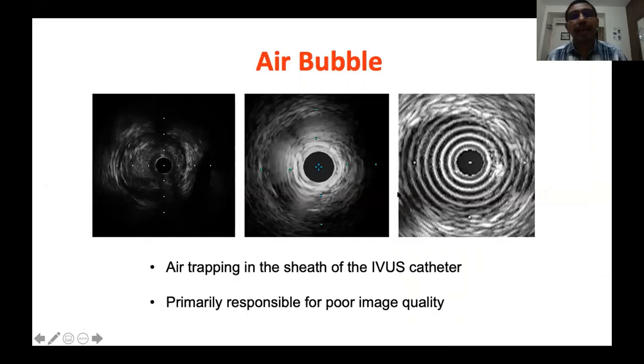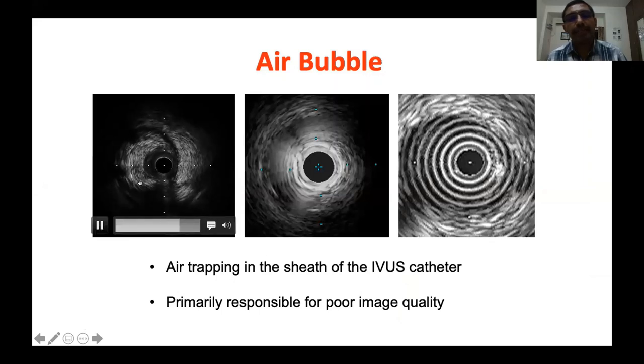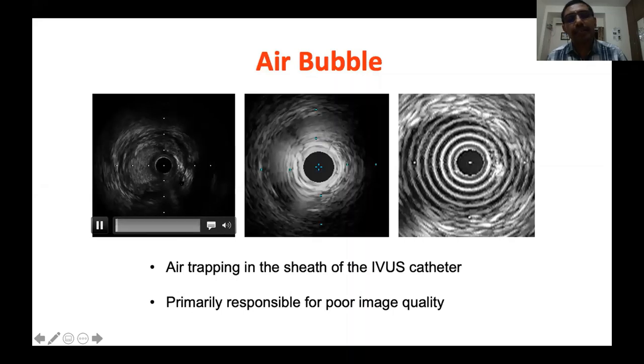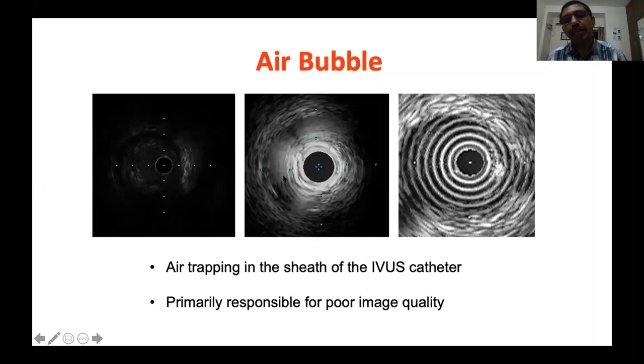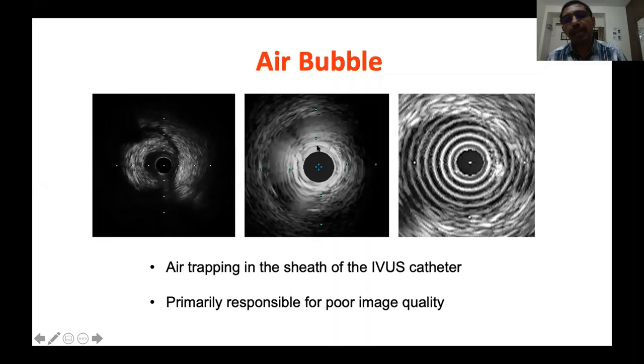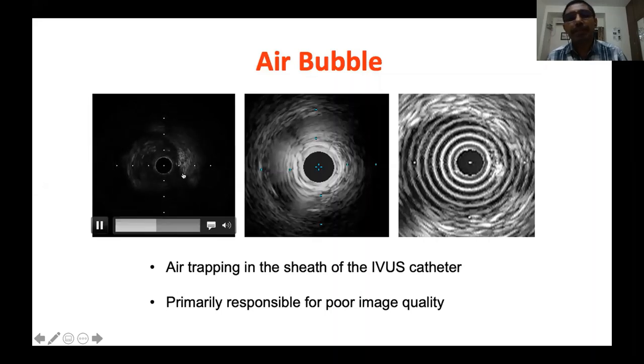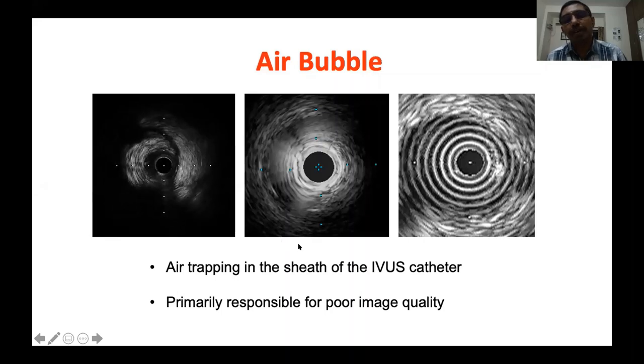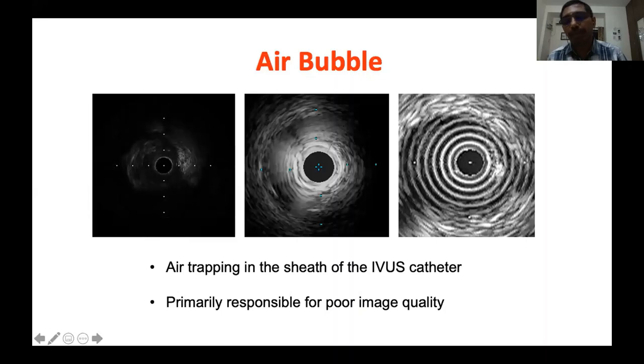Air bubble is the biggest enemy of IVUS imaging. Air trapping in the sheath and IVUS catheter occurs mainly with mechanical catheters — it doesn't occur with solid state systems because there is no sleeve around the catheter. Air bubbles cause diffuse bright appearance — you cannot identify anything — and can also cause prominent reverberations. You must carefully flush the catheter to remove all air bubbles to avoid these types of artifacts.